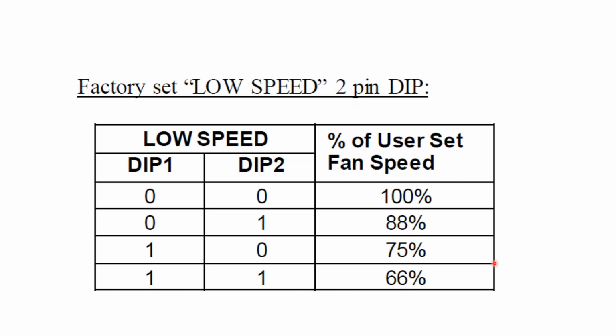So this is how you dial in your low speed setting for heat stage 1 or cool stage 1, and this is giving you your SAV capability. As we did SAV capability on our previous units through the VFDs, this is how we do it on the new EcoBlue Vane-Axial fan and board setup. So it's just that easy. You can set these switches before you adjust your rotary switch and ABC switch, or after, it doesn't matter. And again, you can do these on the fly. Hopefully that clears that one up. Are there any questions on that before we go into the five switch setup?